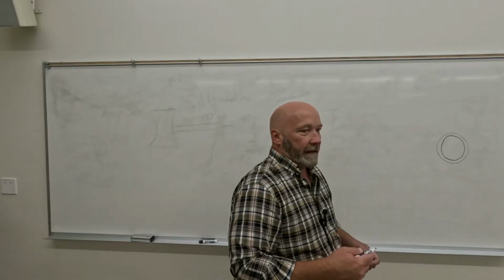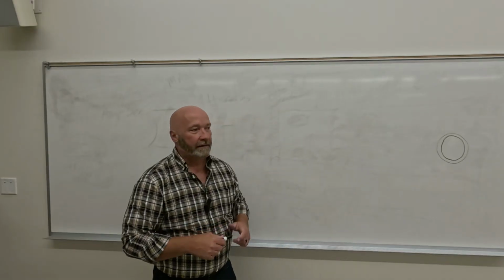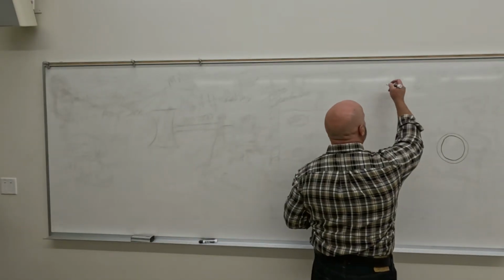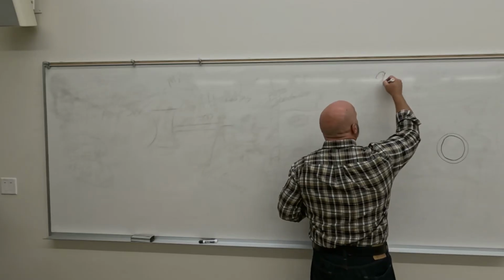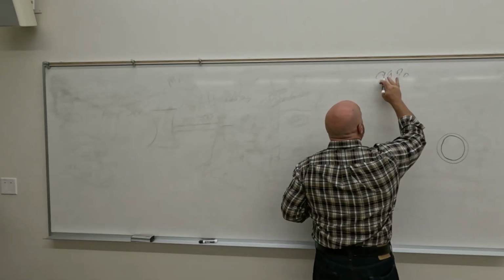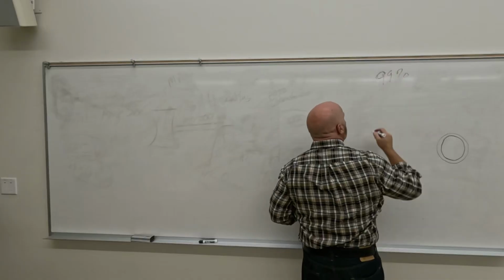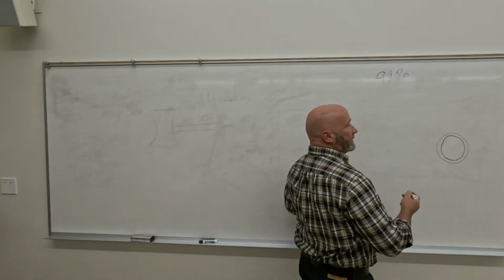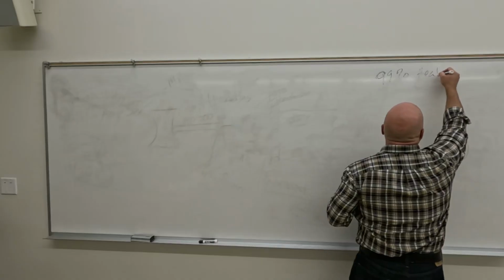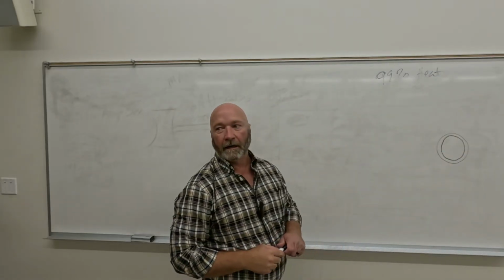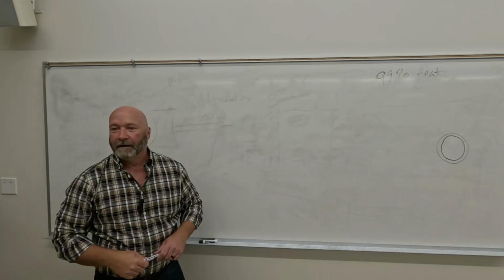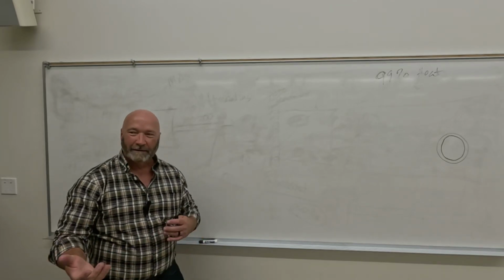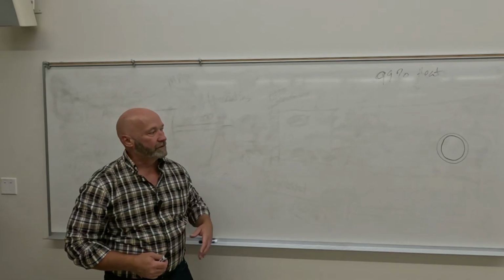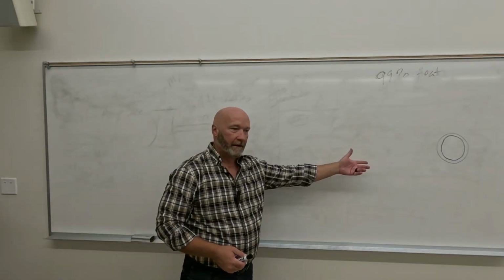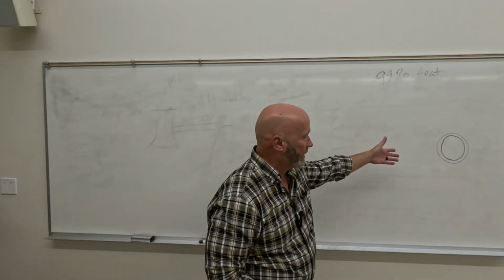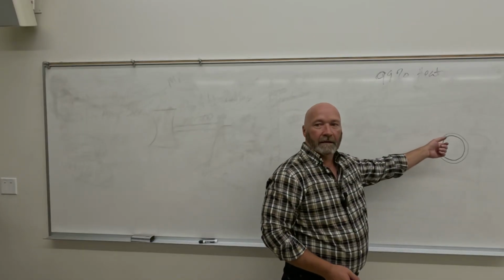The reason we rotate the anode is to disperse heat. And the reason that's important is because upwards of 99% of what we create in the X-ray tube is not X-rays. It's heat. So what happens if you get something too hot? It melts, right. So we've got the filament creating a lot of heat. We send these electrons across the tube that smack into that thing. Anytime you have friction, and electrons are going to create friction, what are you going to create? Heat.